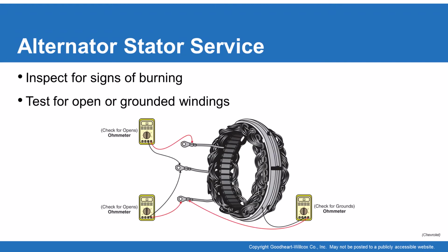In order to check the stator of this unit, we want to use our ohm meter, and we're going to inspect for signs of burning. What we're really looking to do is test for opens or grounded windings. Are they shorted together, and is there excessive resistance between those windings on this unit? Believe it or not, this is the same exact test that we do on larger motor generators that are found in hybrid vehicles. This is a three-phase unit. It's a smaller unit, but the principles are the same.